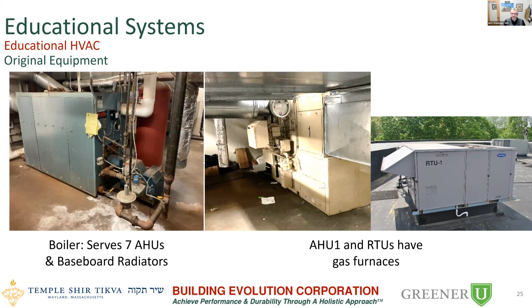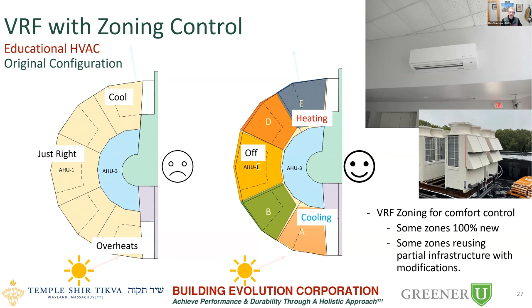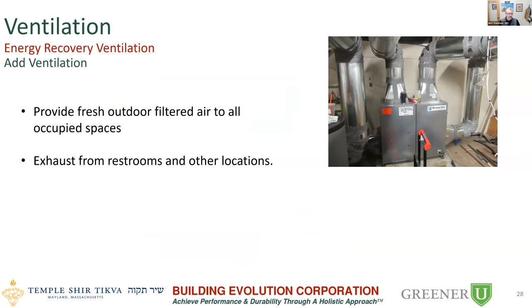At the same time, we wanted to improve comfort and indoor air quality. Looking at those same classrooms, that was an opportunity to rezone, so each classroom now becomes its own zone for temperature control. Remember, a variable refrigerant flow, or VRF, heat pump system is a comfort system, a temperature control system. Each classroom can independently control temperature. This is a heat recovery VRF. All these classrooms are also now provided with fresh air and exhaust going through an energy recovery ventilator, increasing indoor air quality. And the exhaust is now reducing the load because it's transferring through an ERV instead of just being exhausted to the exterior of the building.